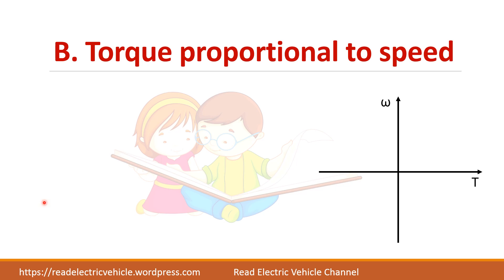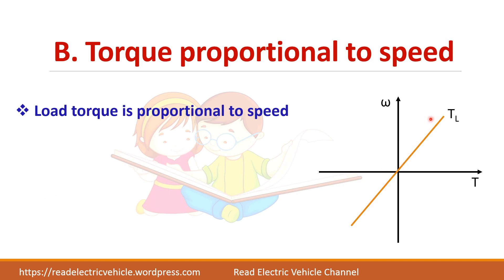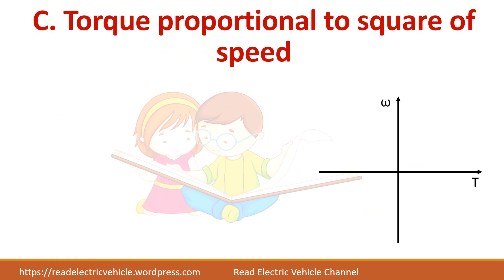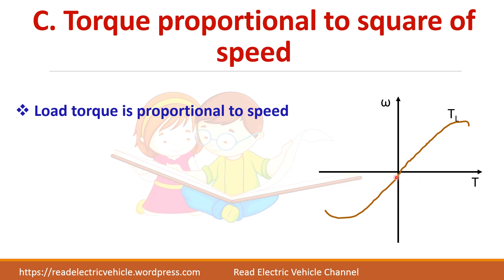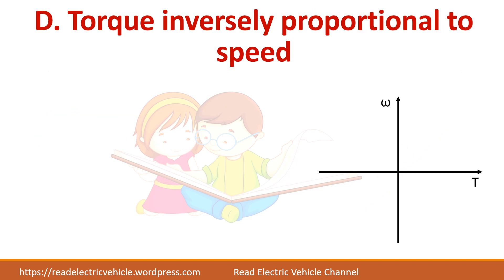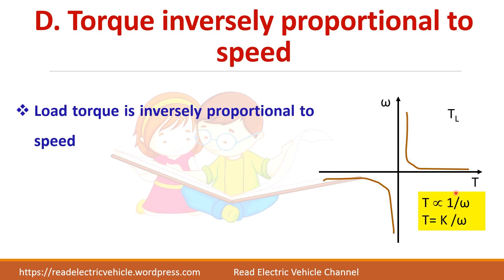The second type is torque proportional to speed: T = k·ω. This is available in eddy current brakes. The third type is torque proportional to the square of speed: T ∝ ω². This curve is found in fans, pumps, and compressors.